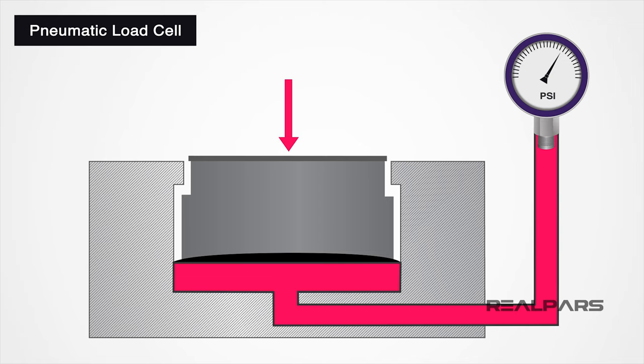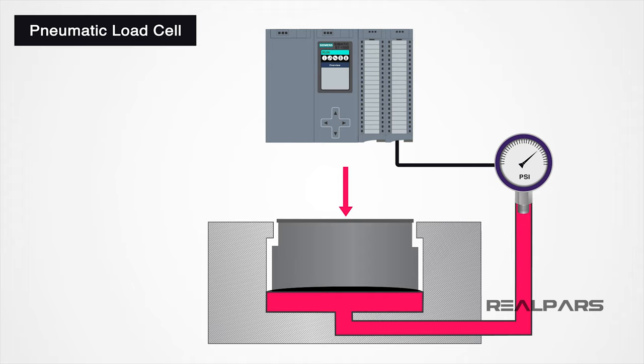When a load is placed on the loading platform, the piston applies pressure to the liquid contained inside it. The pressure increase of the liquid is proportional to the applied force or weight. After calibrating the pressure, you can accurately measure the force or weight applied to the hydraulic load cell. The pressure reading can be read as an analog gauge or it can be converted into an electrical signal from a pressure sensor.